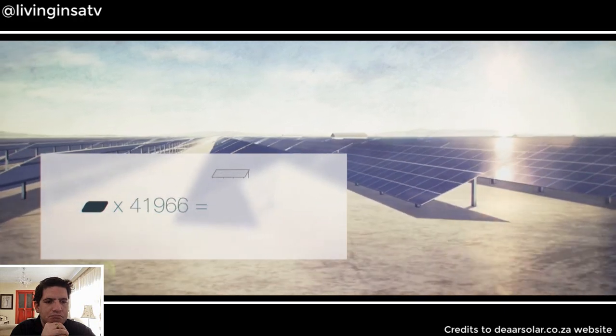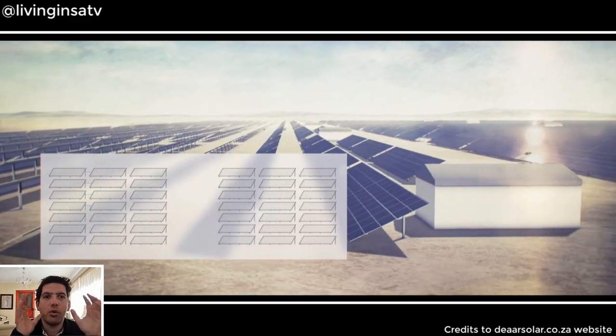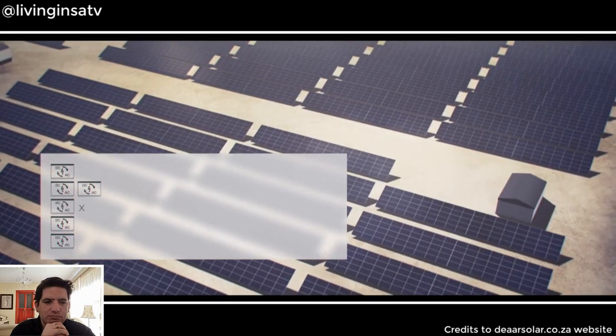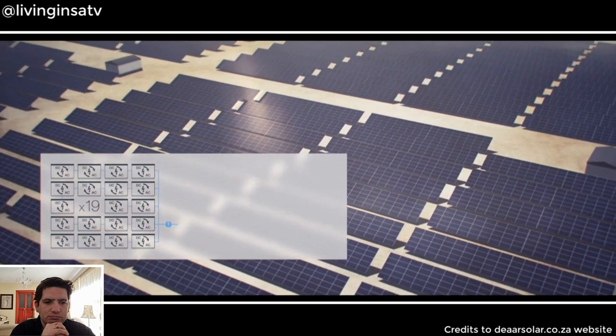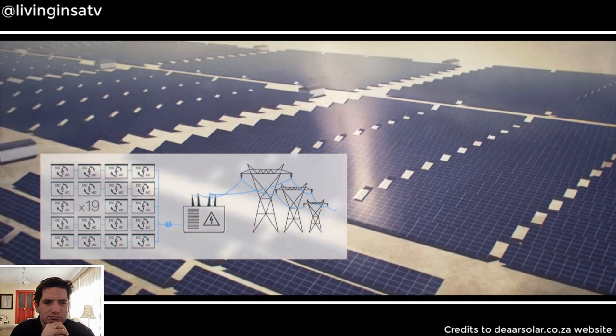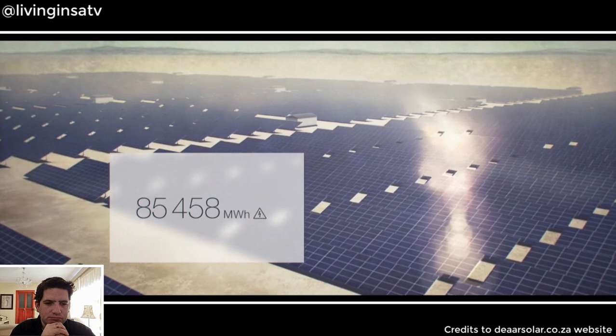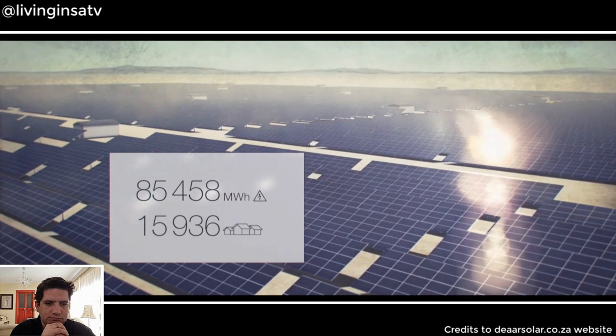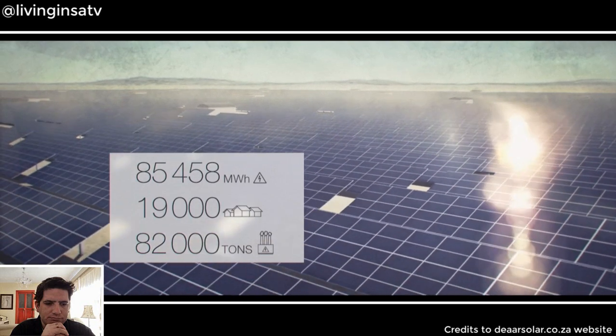In the De Aar facility, there are 95 modules in each array and 167,580 in total. The direct current generated is carried through wiring to an inverter which converts it to alternating current. There are 19 inverters across the field, all coming together at the substation where power is stepped up from 22 kV to 132 kV and fed into the overhead lines. When operating at full capacity, De Aar Solar Power supplies over 85,000 MWh of clean renewable energy per year, meeting the annual energy needs of more than 19,000 South African homes and avoiding more than 82,000 tons of carbon emissions from fossil fuels each year.